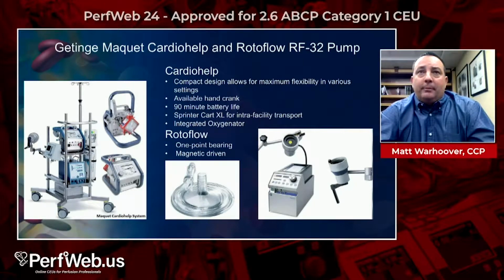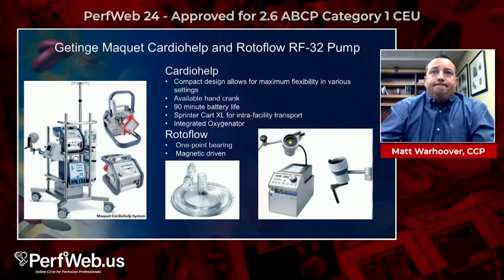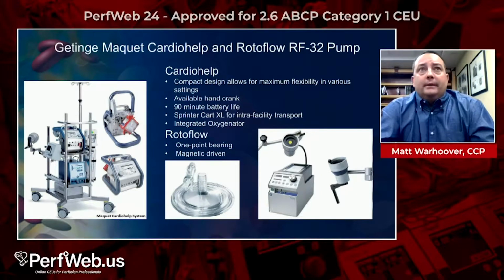And the only downside about the CardioHelp is that anything that needs to be changed out, whether it's the pump head, the oxygenator, even a line, you have to change out. It's an integrated system, so I would say that's the drawback on that system. It's a one and done. One and done, yeah. Next slide. Exactly.